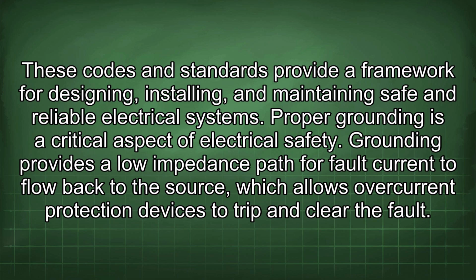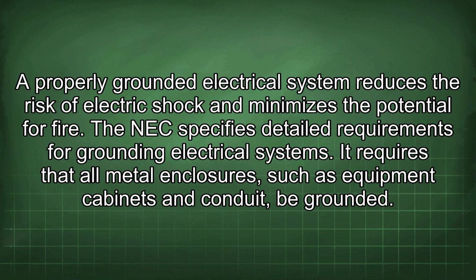Proper grounding is a critical aspect of electrical safety. Grounding provides a low impedance path for fault current to flow back to the source, which allows overcurrent protection devices to trip and clear the fault. A properly grounded electrical system reduces the risk of electric shock and minimizes the potential for fire. The NEC specifies detailed requirements for grounding electrical systems.